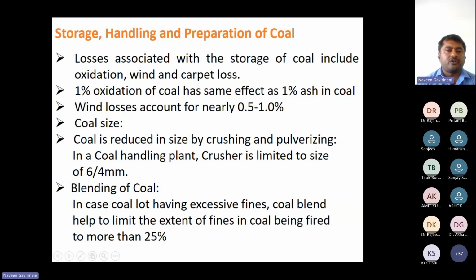The main point in the coal handling plant is storage: how to store the coal and how to utilize the coal. There are many losses associated with the coal handling plant. Those are the oxidation losses. While the coal comes from the supplier, there is some percentage of moisture content. We do not use the incoming coal directly. We keep it in some place for some period of time, and after that we use the coal. If we check the moisture percent then, it will come down to 10 to 12%. So there is a loss due to oxidation. We have considered 1% oxidation loss for the coal.